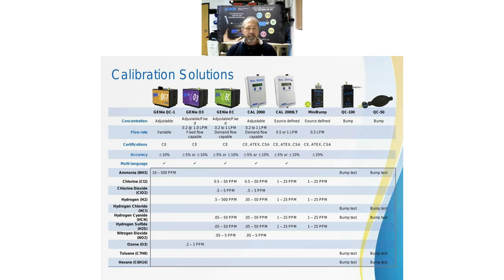And this gives you a reference to what instrumentation we produce that makes the specific gases that you're looking for. These instruments have built-in pumps rather than a compressed gas cylinder where you put a regulator on the top and the gas comes out. These instruments have pumps inside them, and you can set the flow rates, and you can see those vary also, so that you can match up to your specific sensor, whatever that manufacturer recommends to calibrate their sensors. That's what you can set your instrument to give the output you want. And you can vary them. So if you have a certain brand of sensor that wants, let's say, 5 parts per million chlorine at 0.5 liters per minute, you can calibrate all those, and then you can change the output without buying a different cylinder. For example, you just change the output to 10 parts per million, 1 liter per minute, if that manufacturer says that's what they recommend for their calibration.